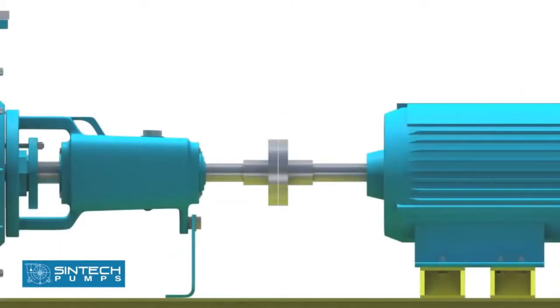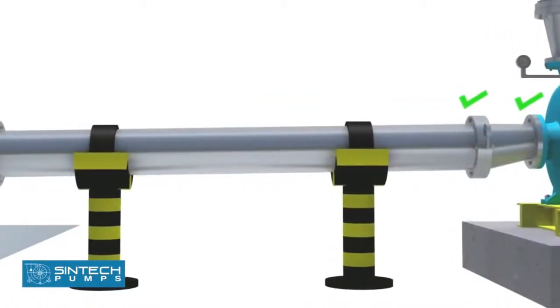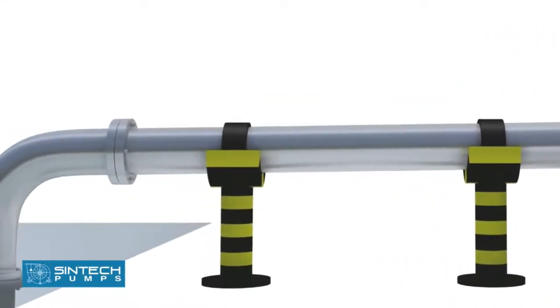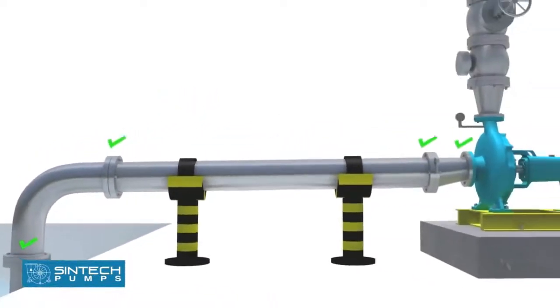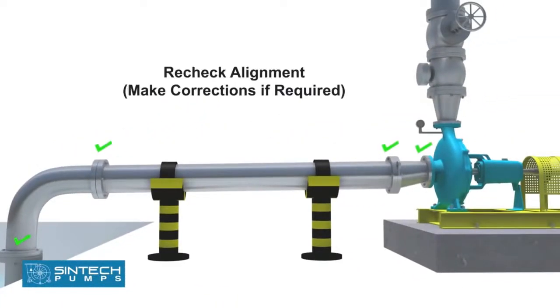Once this is completed, the alignment should be rechecked and similar readings should be obtained. If this is not the case, then the piping should be investigated and suitable corrections should be made. If this is left unattended, it can cause stress on the pump casing.